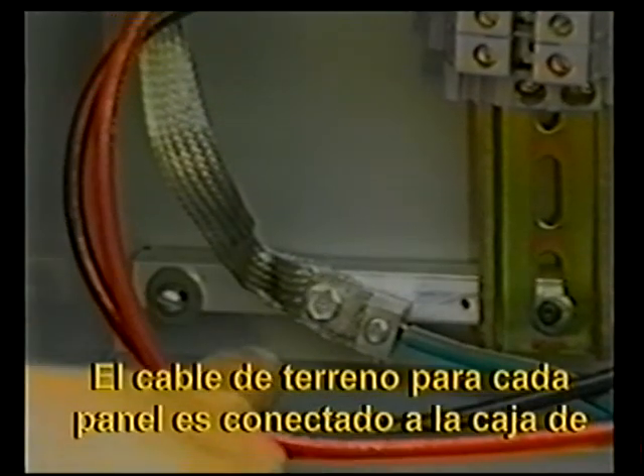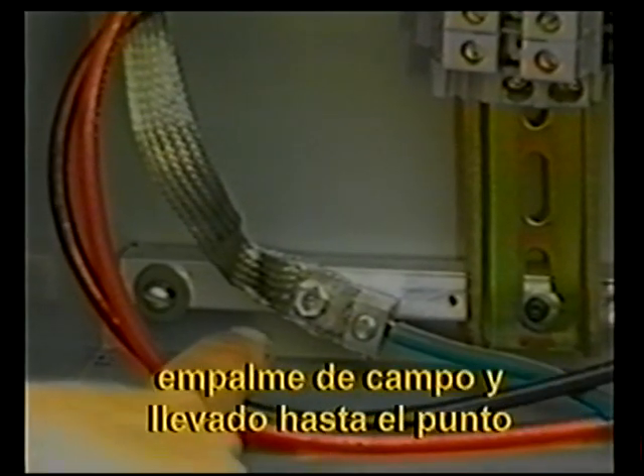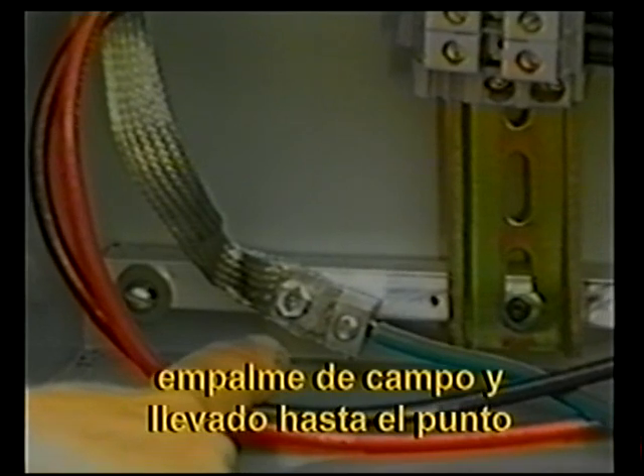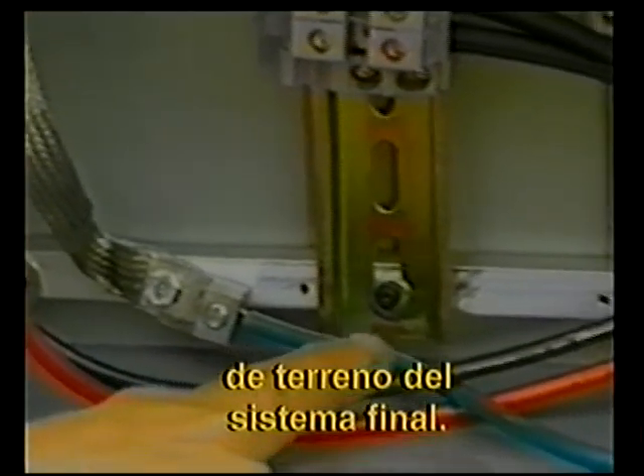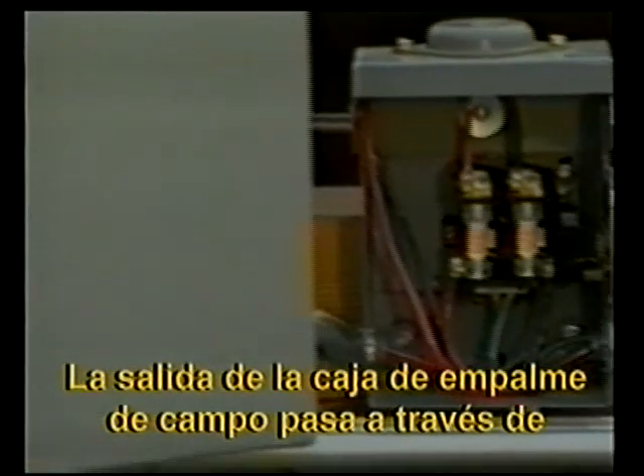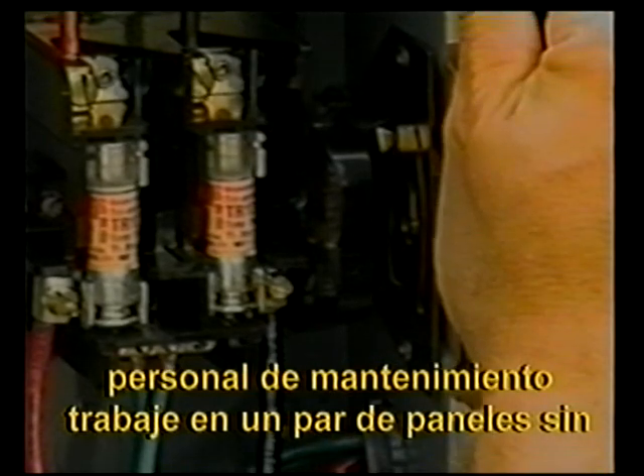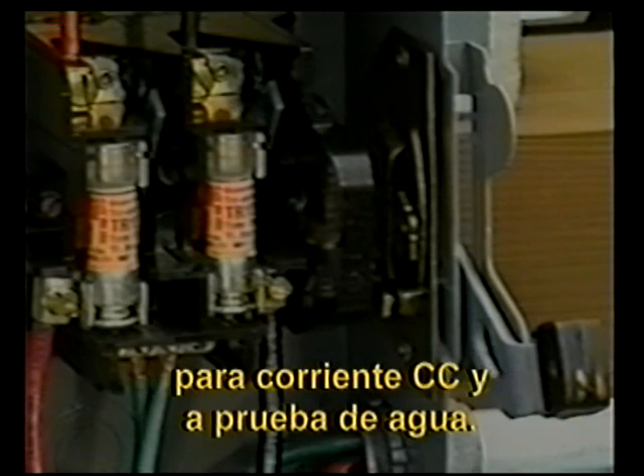The ground wire for each panel is connected to the field junction box and carried through to the final system ground point. The output from the field junction box passes through a fused disconnect switch to allow maintenance personnel to work on a pair of panels without interrupting the output from the rest of the array. These disconnect switches must be rated for DC current and should be water resistant.